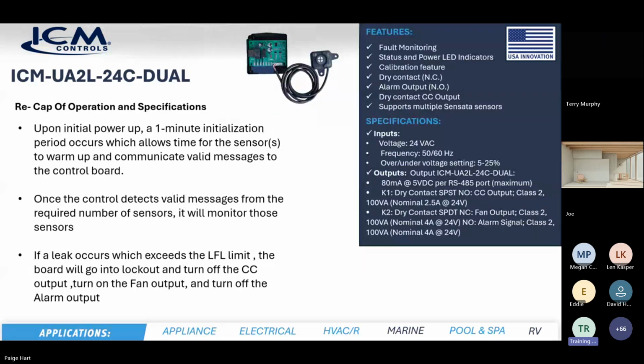And also, don't forget, this board comes with dual sensor applications as well. I don't know if you can see it in that picture, but there are 2 ports for sensors. So let's say you have a big commercial system and you needed more space, right? Your coil was so big that you couldn't fully protect yourself with just one sensor. You can add another sensor, and now you have over a 12-foot span that you could cover, mounting the sensor here and another sensor over here to the left. So you can cover the entire coil rather than just hoping that the leak is going to be on one side. Now, if it gets really, really big, you can also order another board and you'll get 2 more sensors. So you could have multiple locations to place sensors and sense leaks. You have to cover the whole coil when you're sensing leaks.